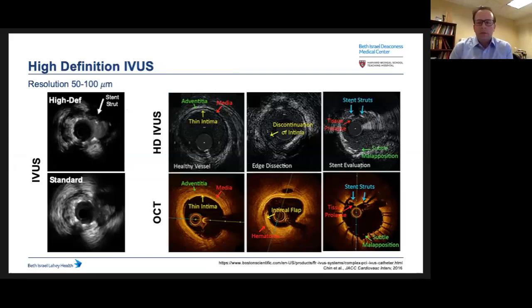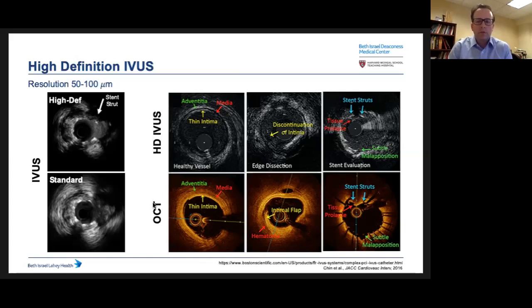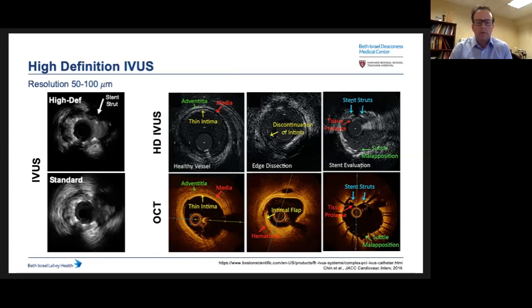In an attempt to compete with OCT, IVUS has developed better resolution systems using higher-frequency 60 MHz transducers, with a tradeoff of slightly decreased field depth. Stent visibility is improved with high-definition IVUS compared to standard IVUS, and we're better at identifying dissections and possibly thrombus. However, compared to OCT — which has much better resolution — things like intimal flaps from dissections are much easier to see with OCT, as well as more subtle aspects like malaposition, where stent struts aren't fully apposed to the vessel wall, or tissue prolapse between struts.